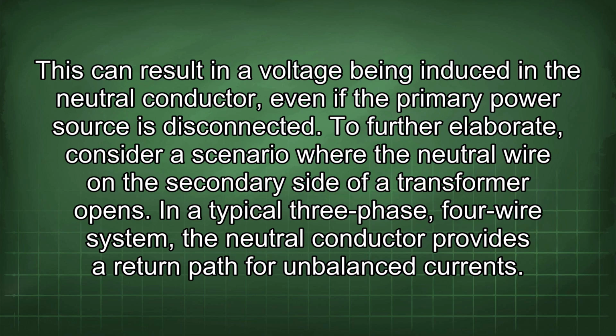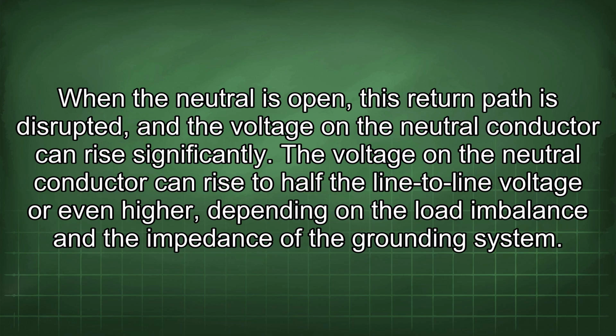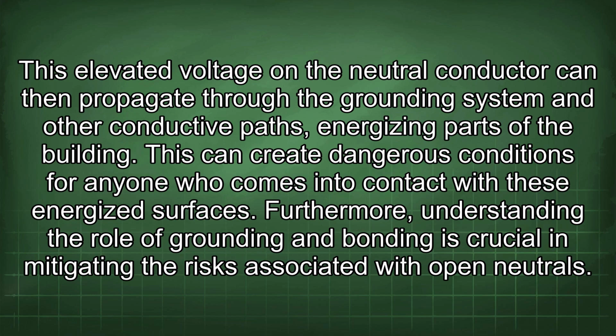To further elaborate, consider a scenario where the neutral wire on the secondary side of a transformer opens. In a typical three-phase, four-wire system, the neutral conductor provides a return path for imbalanced currents. When the neutral is open, this return path is disrupted, and the voltage on the neutral conductor can rise significantly. The voltage on the neutral conductor can rise to half the line-to-line voltage or even higher depending on the load imbalance and the impedance of the grounding system. This elevated voltage on the neutral conductor can then propagate through the grounding system and other conductive paths, energizing parts of the building. This can create dangerous conditions for anyone who comes into contact with these energized surfaces.